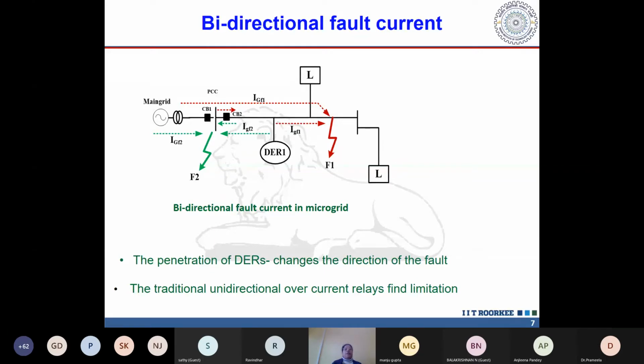I have marked a small component here for understanding, this red arrow shows the direction. Every circuit breaker has a CT near it, and the CT sees the current direction from upstream to downstream normally, but for this fault it sees the opposite direction. So the polarity changes and the angle also changes. This is how the penetration of DERs changes the direction of the fault.